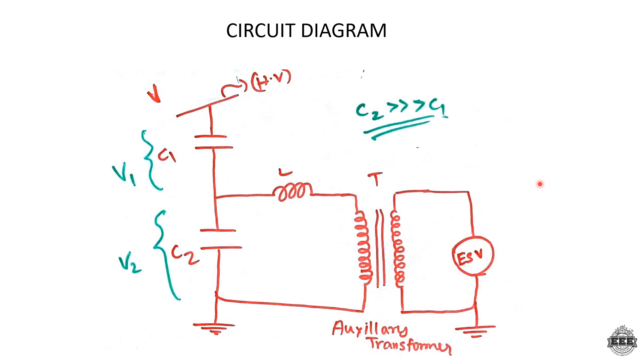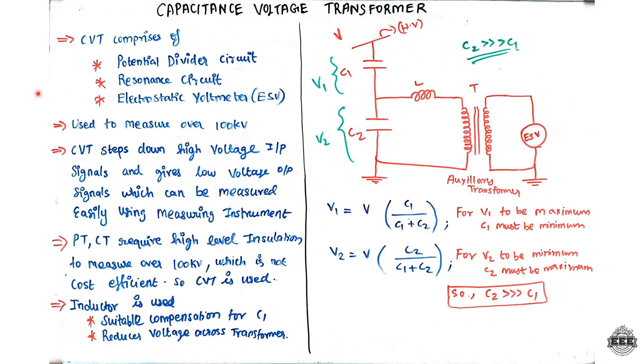One of the most common applications of a Capacitance Voltage Transformer is voltage measurement on high voltage power lines, such as lines over 100KV. The CVT comprises a potential divider circuit where voltage V1 and V2 are divided - V1 plus V2. The resonance circuit, capacitor, and electrostatic voltmeter together allow measurement over 100KV.